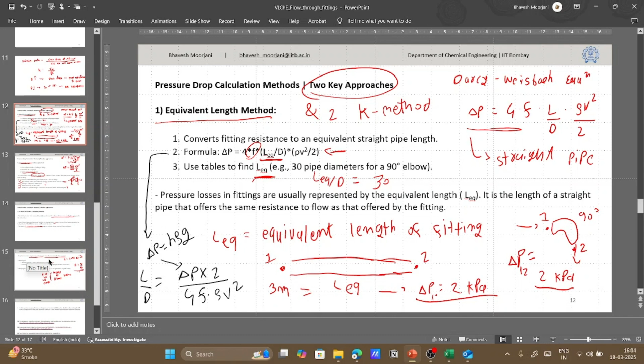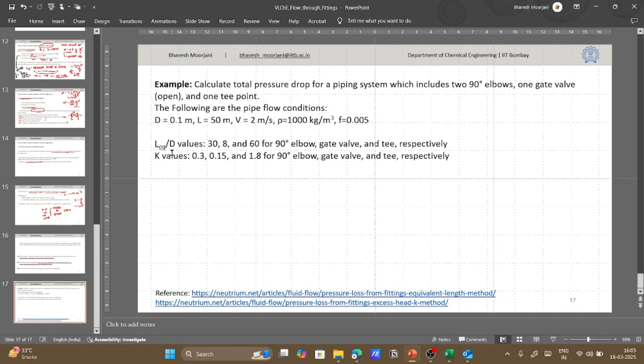And let's say once we have this information, what did we do from this experiment? We computed delta P and backtraced to find L equivalent, right? But in actuality, for a given fitting or a given bend, a given 90-degree elbow or a given valve, we will have either K equivalent data or L equivalent by diameter value, and we want to compute what the pressure drop will be because of this particular fitting, right? So in that case we will use this information and calculate the pressure drop. So I have kept an example problem for that.